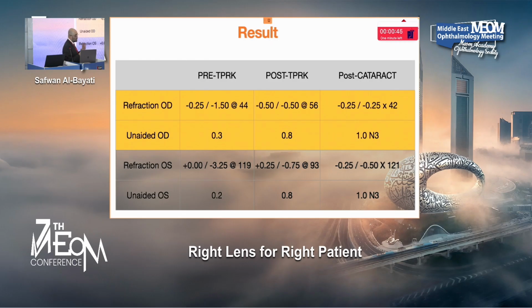I don't have any financial disclosure. When you change, because I kept the two machines with me for more than 7 months, I found the difference is in the axial length, the ability to measure the proper axial length, the depth of the measurement when it passes to the retina, with IOL Master, to the surface of the retina. So that gives you the confidence to reach the target.